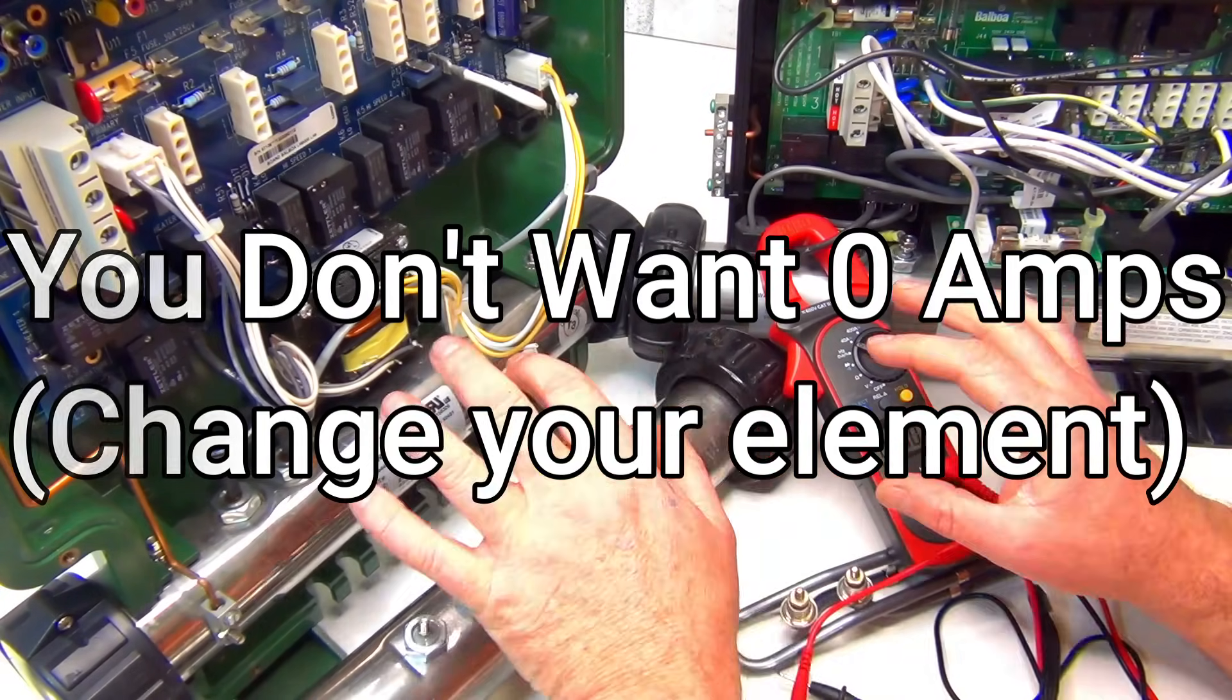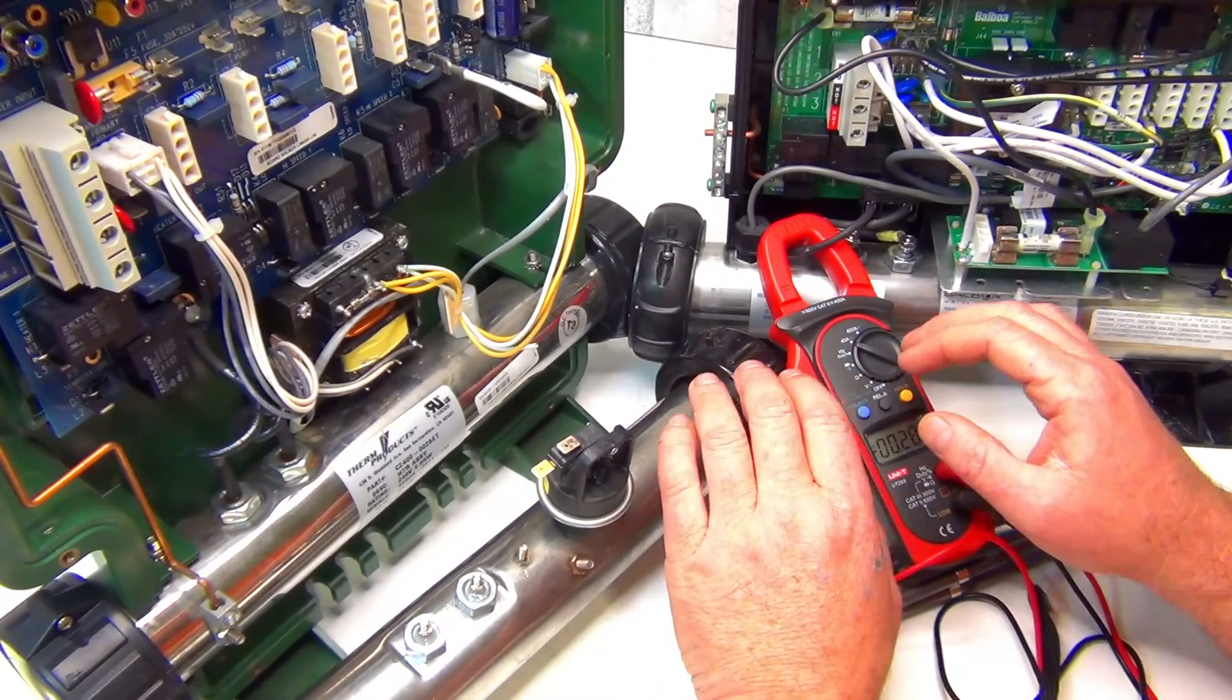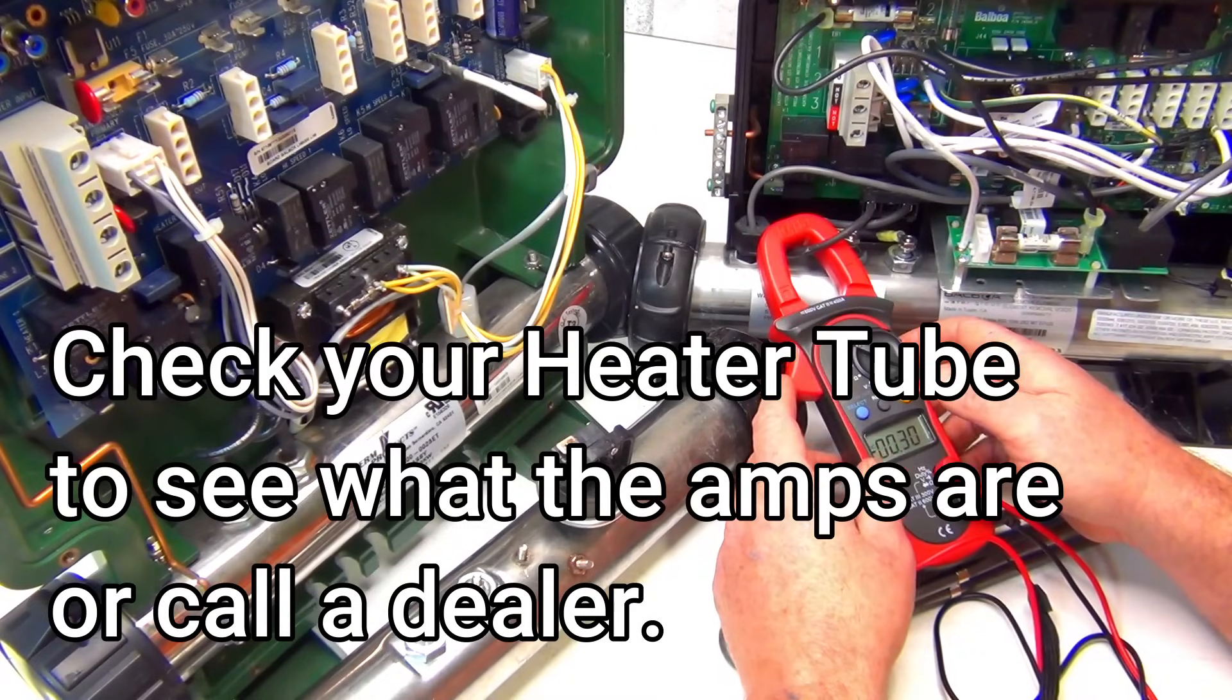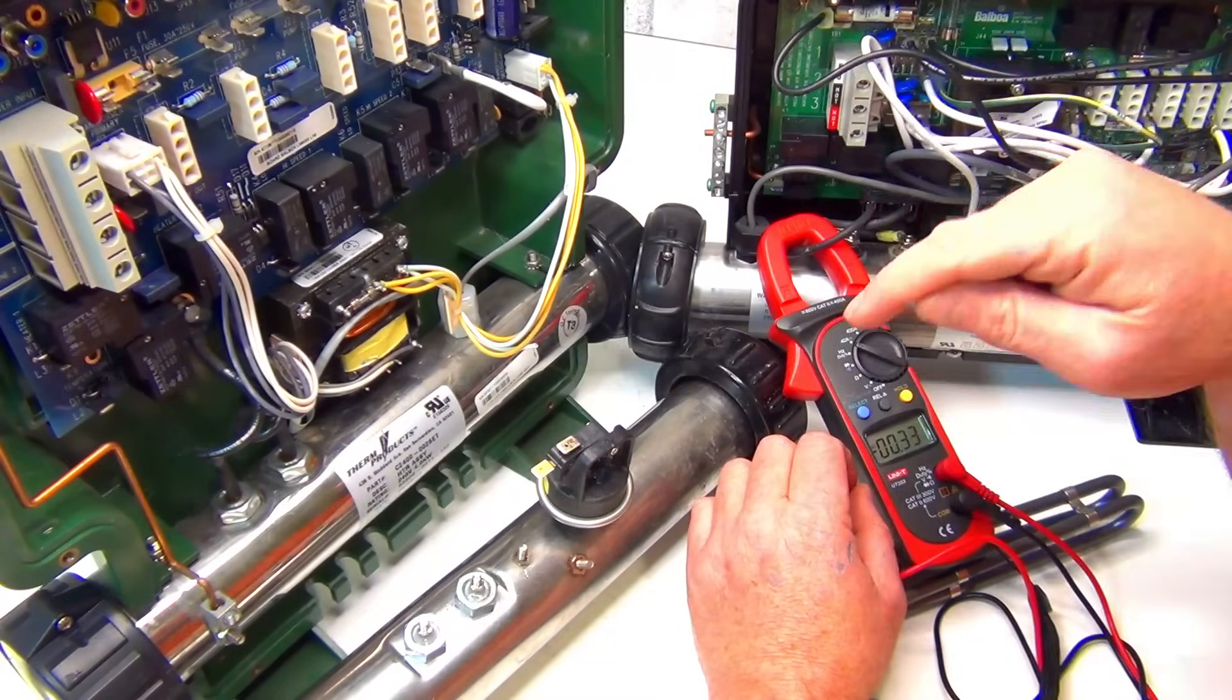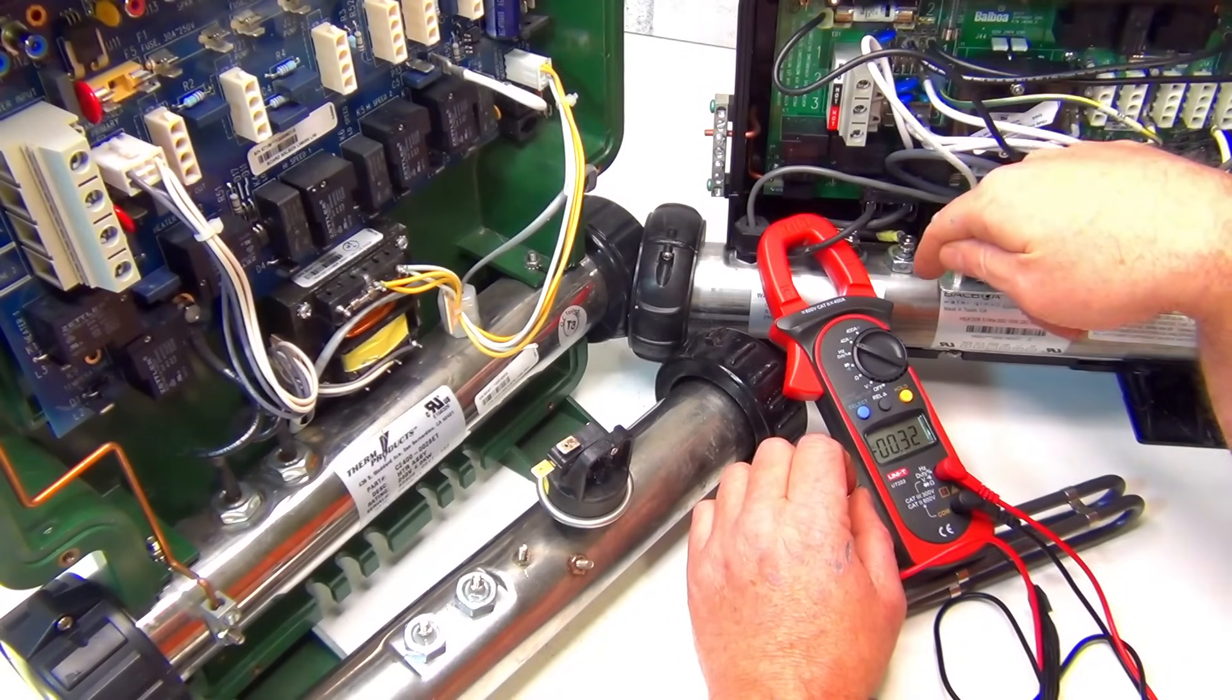Now it depends on what heat tube you have. You've got to check to see what the amperage is or what it should be. If you get zero amps with the power on, change the element.